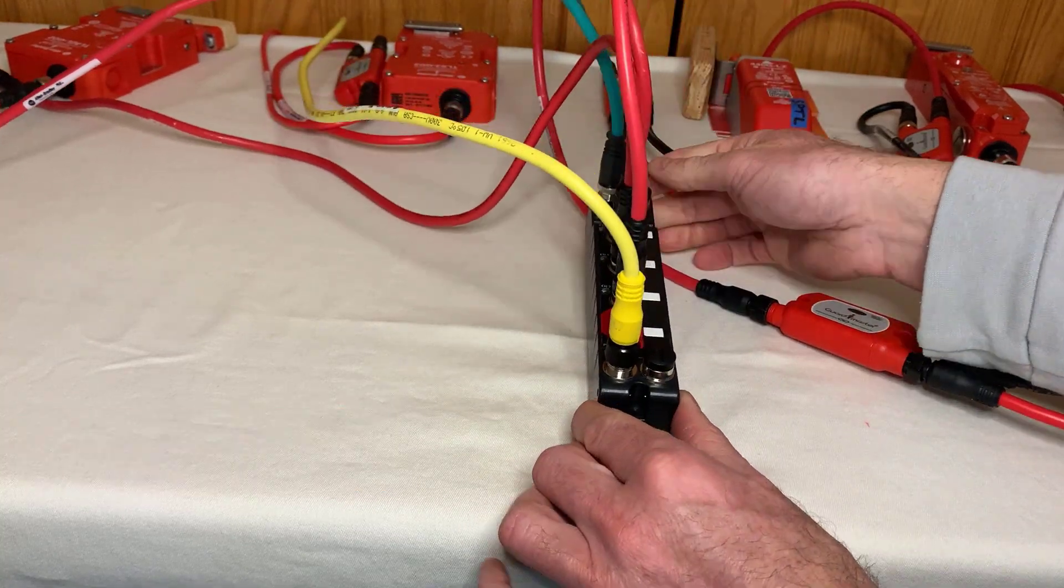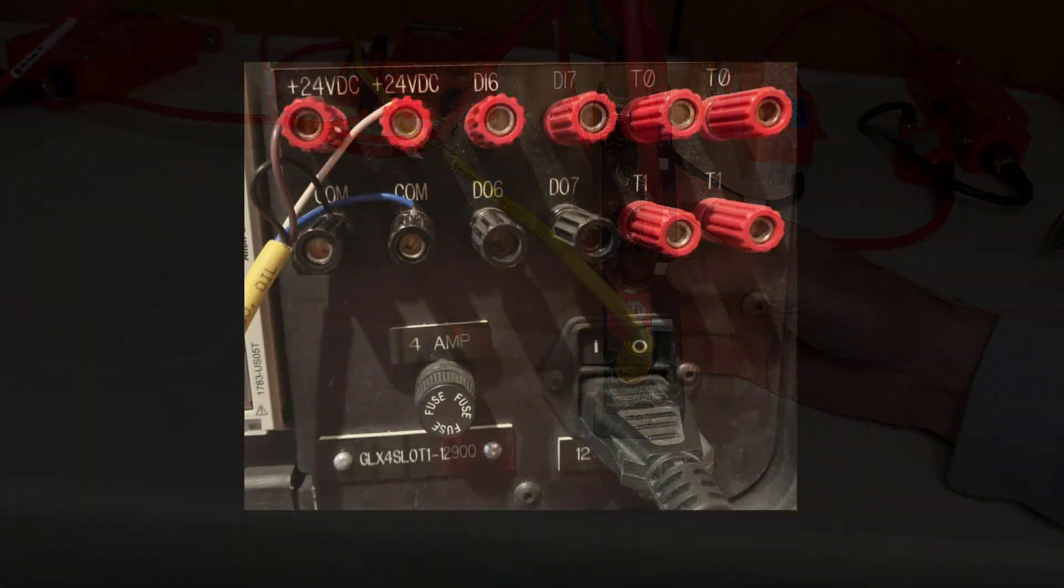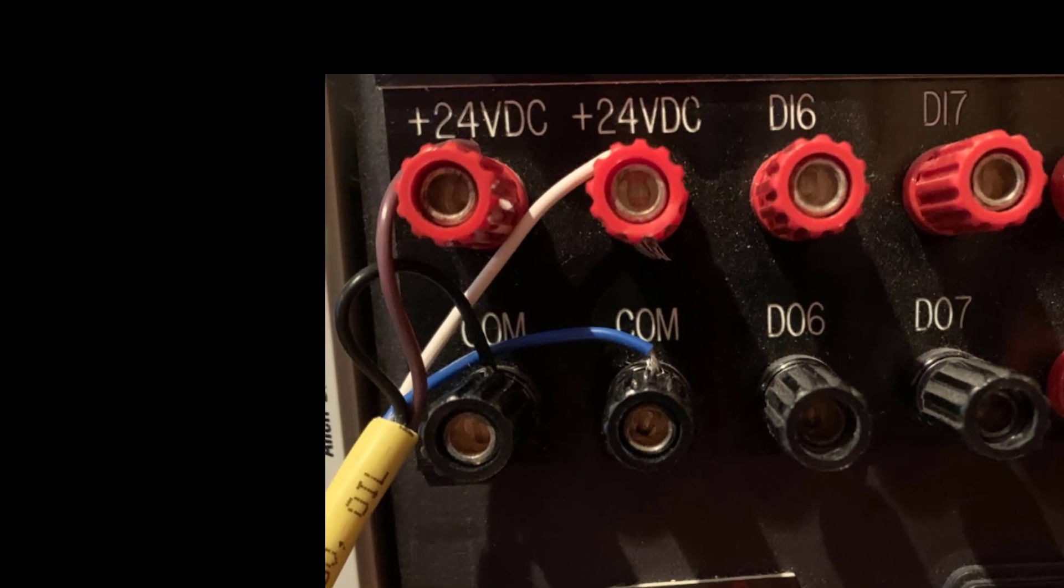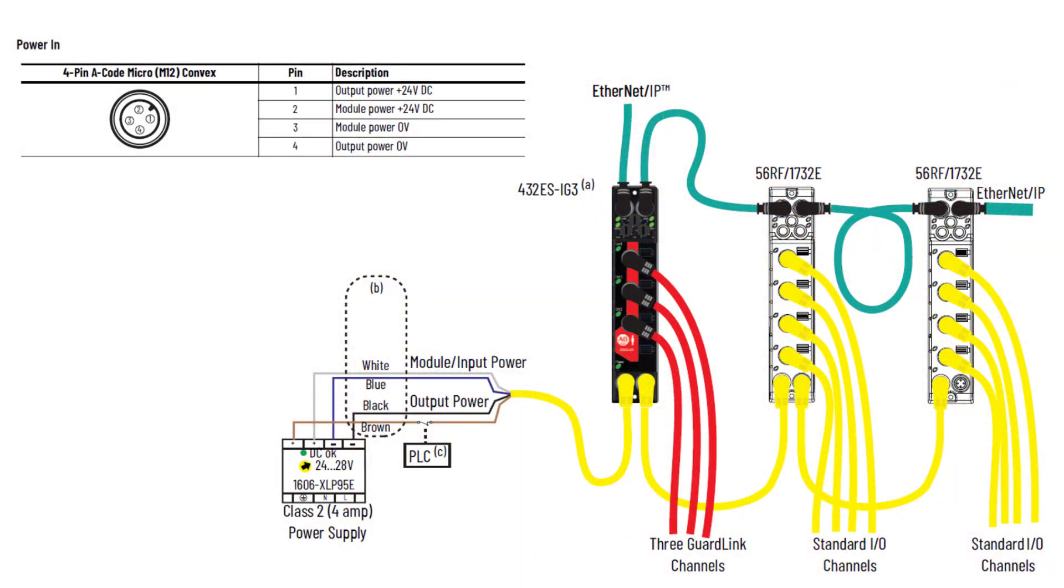The power supply may be the only wiring in a GuardLink system where pluggable patch cords are not used. Interesting enough, this is the only place where I made a wiring error. So let's look closely at the power supply wiring. The GuardLink interface only uses module input power coming in on pins 2 and 3, or the white and blue wire of a typical power cable.